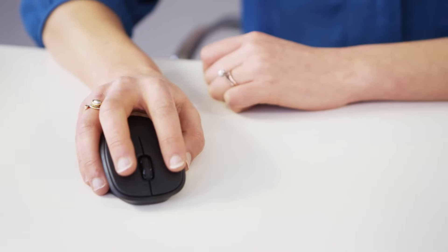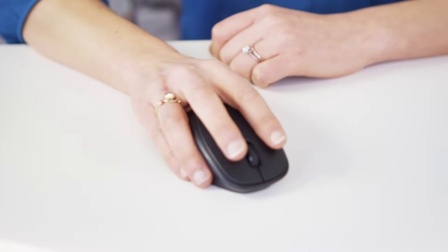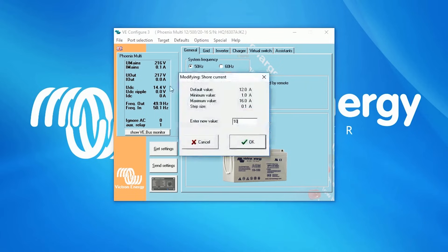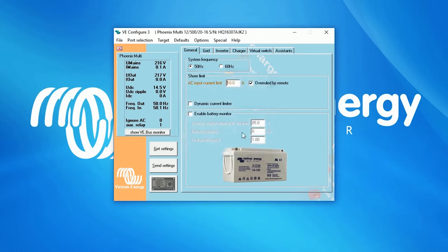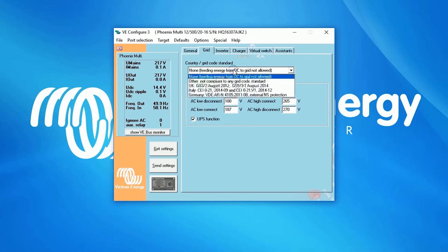In the first tab, you can choose some general settings, such as system frequency. When a setting is changed from the default to another setting, the text will become red, which means the changed settings have not been uploaded into the VE Bus product yet. We'll explain how to upload these changed settings later. The Grid tab enables you to choose your country grid code standard, as the safety protection rules are different for each country.